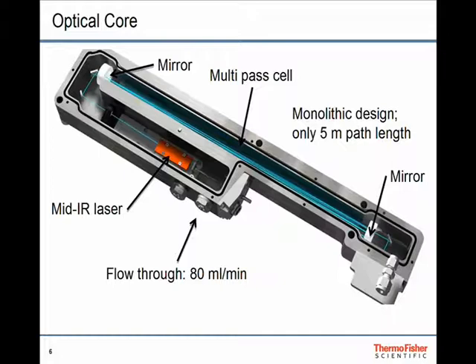The other thing to point out is, like most of these optical analyzers, they operate in a flow-through mode, meaning there's a continuous flow of sample through the cell where the interaction of the light with the sample occurs. Specifically in our analyzer, it's about 80 milliliters per minute that continuously flow through. That also means if you have a change in your sample, it takes some time for that to show up in the signal because first you need to completely replace the sample in the cell. That's something to keep in mind that's quite different from a typical mass spec setup.